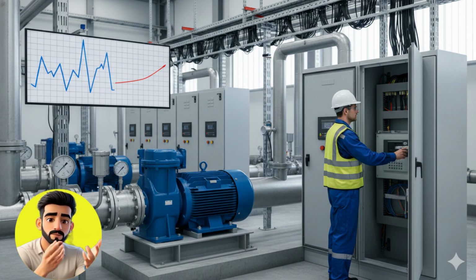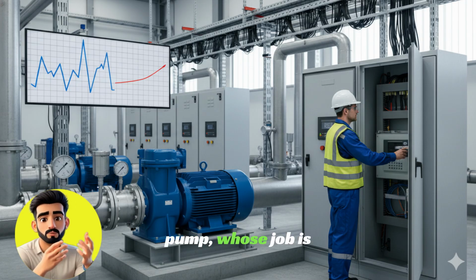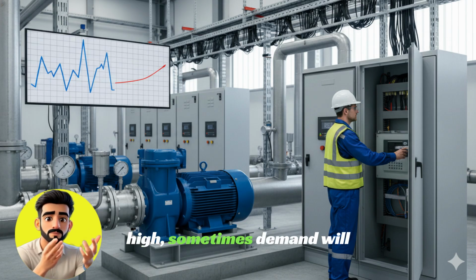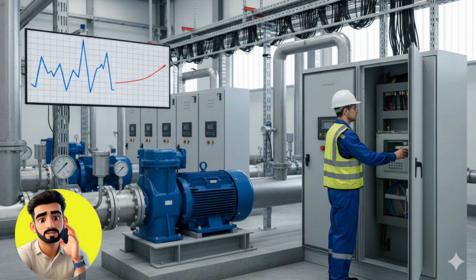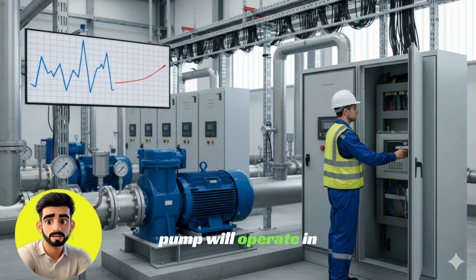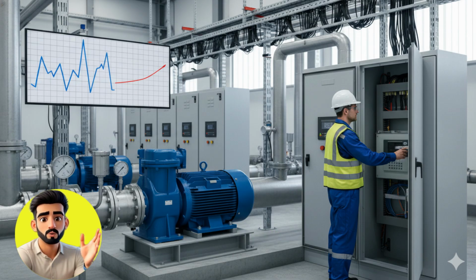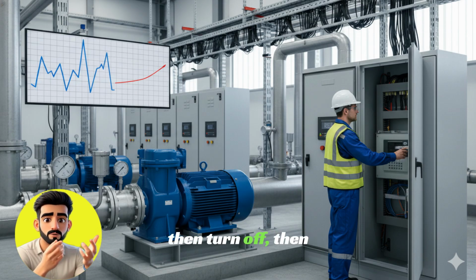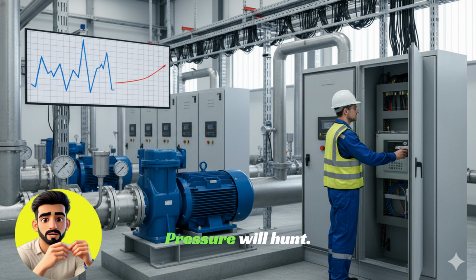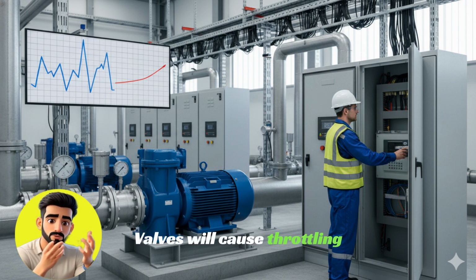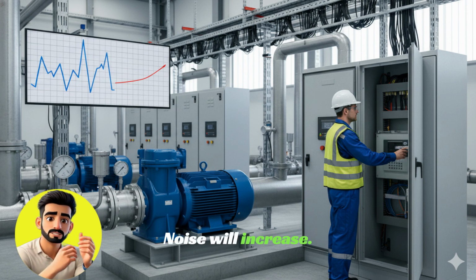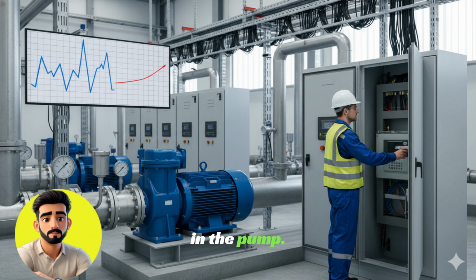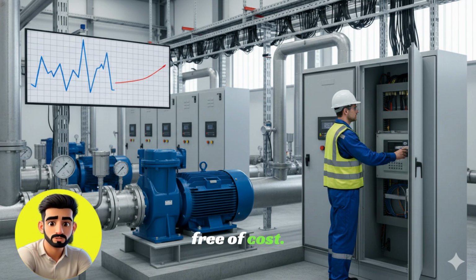Imagine a simple example. You have a booster pump whose job is to maintain discharge pressure. Sometimes demand will be high, sometimes demand will be low. If you are using a soft starter, the pump will operate in only two states, either at full speed or off. What will be the result? The system will turn on and off repeatedly, then turn off, then turn on again. Pressure will hunt, valves will cause throttling losses, noise will increase, and surging may start in the pump. All these problems come free of cost.